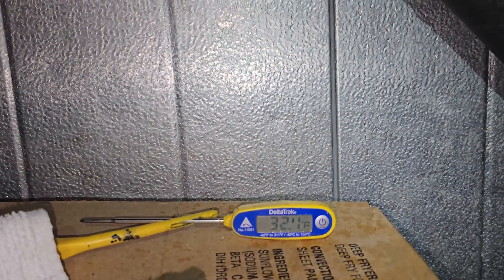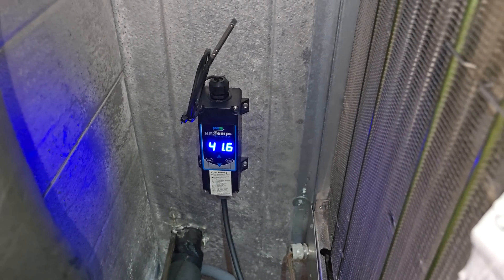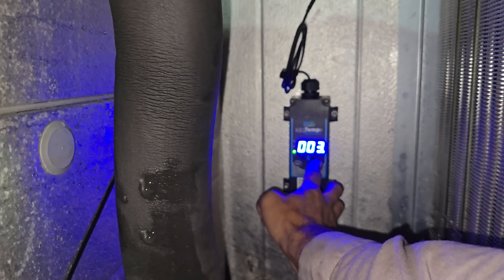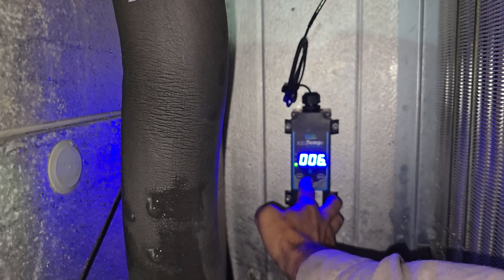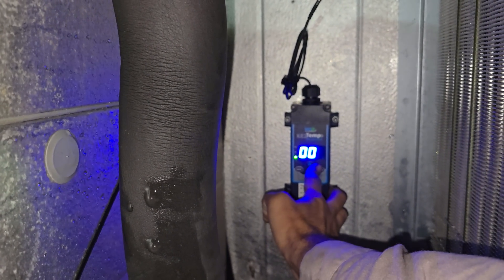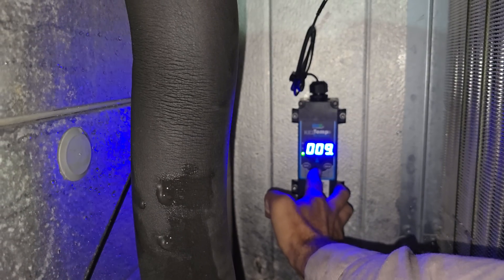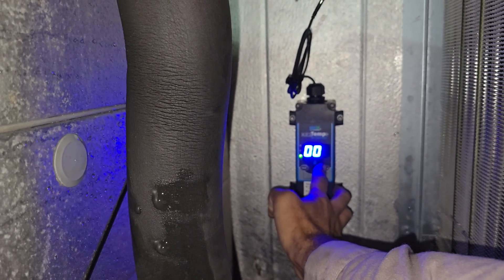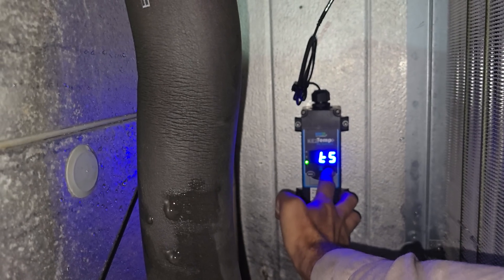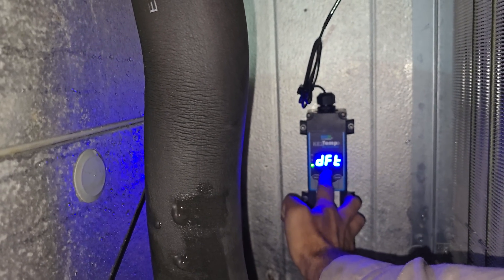So this guy says about 31 degrees. Give it a few minutes to get some air moving. It just came on. We set it for negative 10. Differential — we're going to set it for 3. Compressor starts per hour is off. Defrost per day is zero. Defrost time: zero. T5 negative 10, differential 3, everything else is off — compressor starts per hour, defrost per day, defrost time. We're good. So this guy's ready.